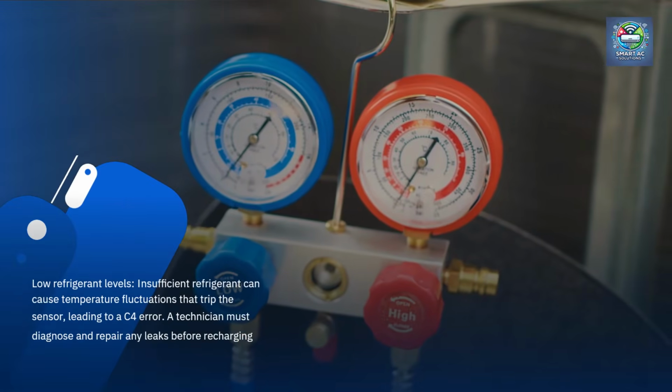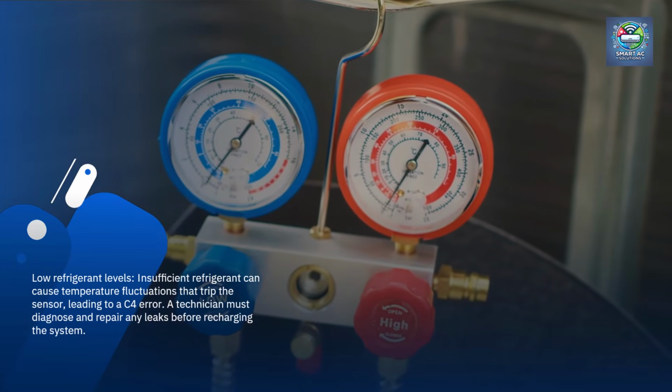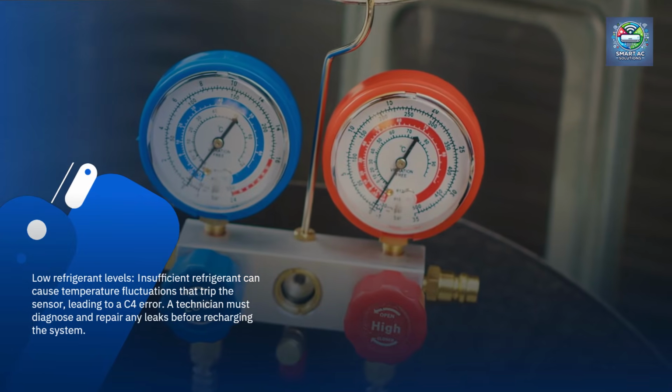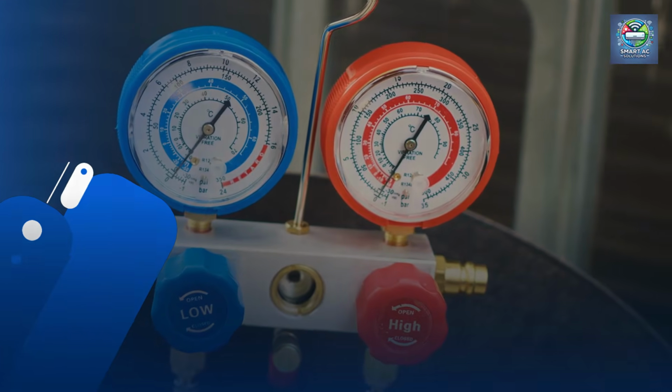Low refrigerant levels. Insufficient refrigerant can cause temperature fluctuations that trip the sensor, leading to a C4 error. A technician must diagnose and repair any leaks before recharging the system.